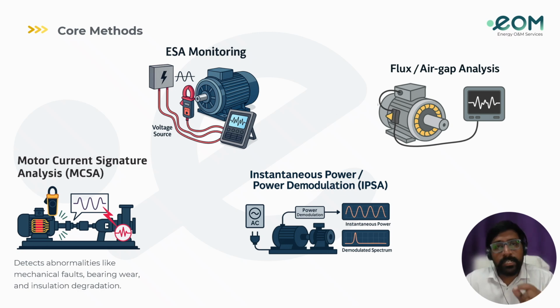If you see a steel mill that alternates between light and heavy slab loads, currently only FFT gives mixed results. Switching to power-based demodulation in the relay yields consistent detection of developing rotor issues as well.